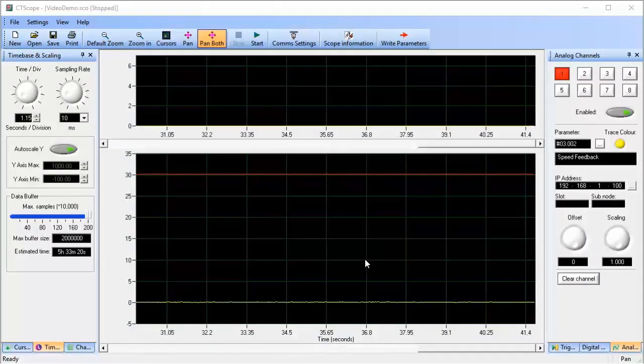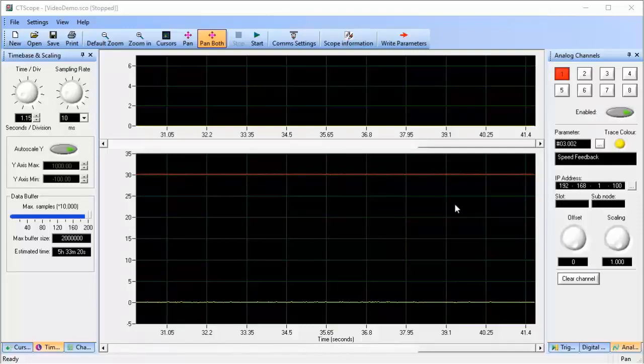I'm connected to my Unidrive M700 using Ethernet. While CT Scope works over RS-485 too, unless you have the baud rate in the drive adjusted to one of the higher rates, the scope traces you see will tend to be choppy.